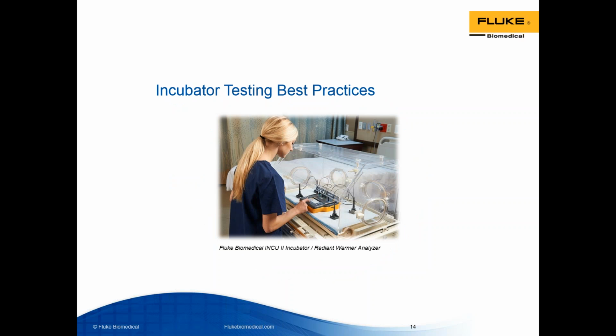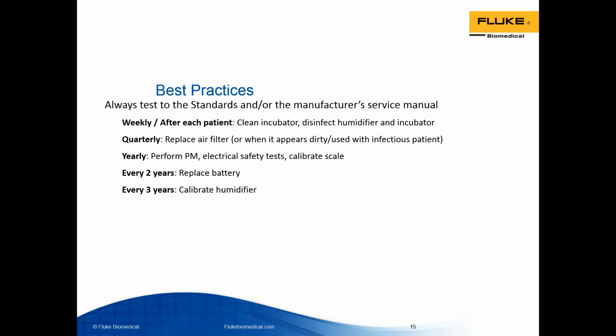So now that we've reviewed the background, the basic functionality, and the reasons to test infant incubators in the first place, let's now discuss what some of the best practices are for testing these infant incubators. First, be sure to always complete the performance inspection either per the standards and/or the manufacturer's procedure. These will often include weekly or after-each-patient-use checks, quarterly checks, yearly preventative maintenance schedules, and then also replacing the battery usually every 2 years, and calibrating the humidifier every 3 years.